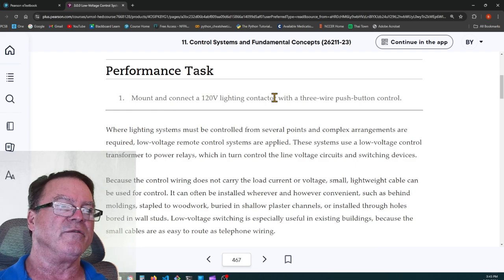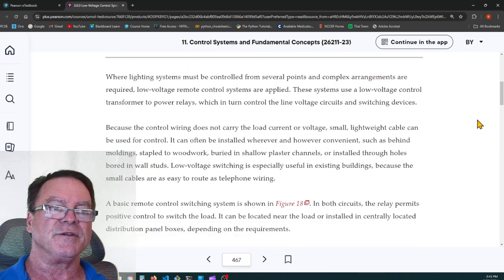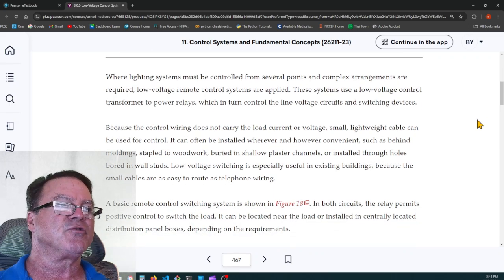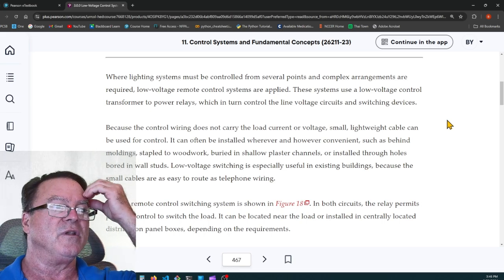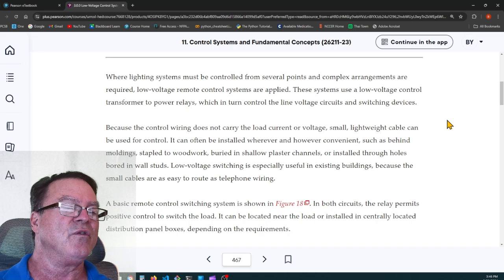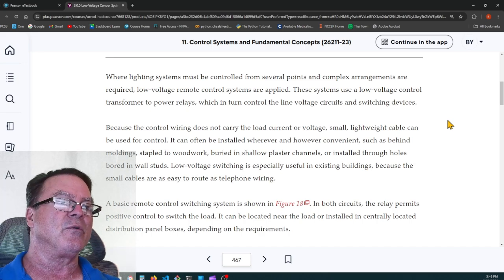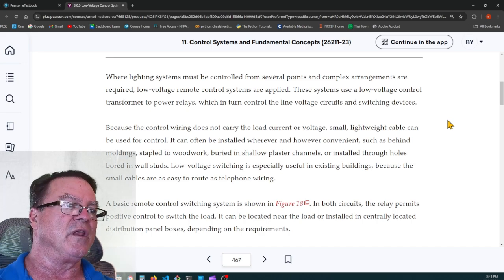Mount and connect a 120 volt lighting contactor with 3-wire push button control that your instructor might want you to do. Where lighting systems must be controlled from several points and complex arrangements are required, low voltage remote electrical control systems are applied.